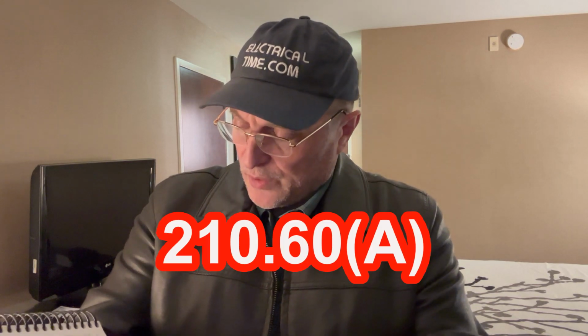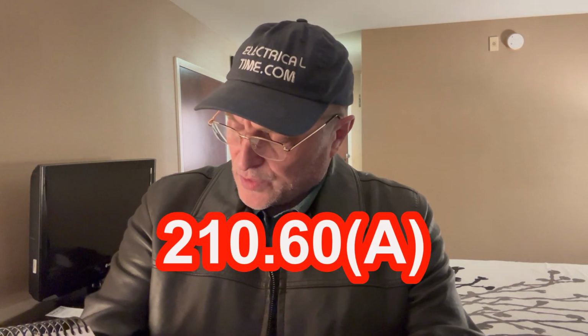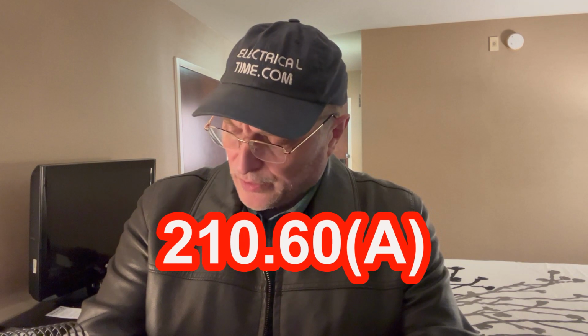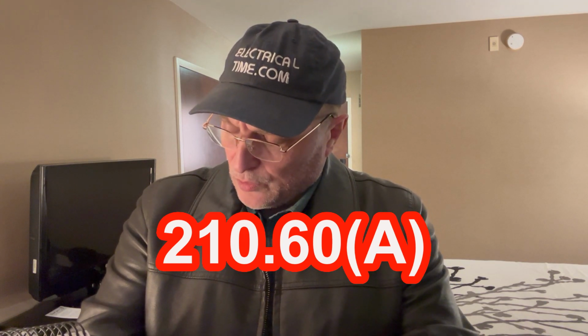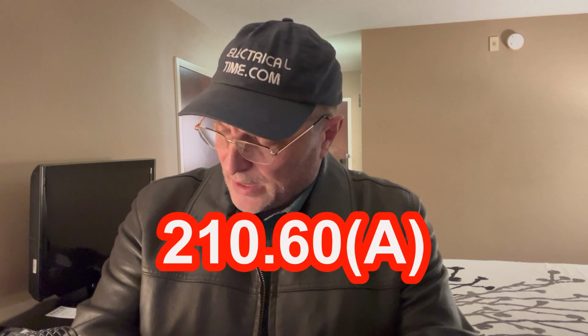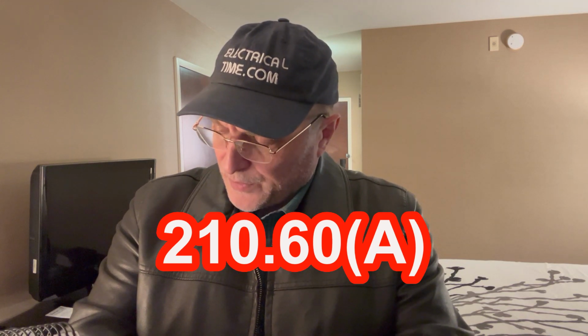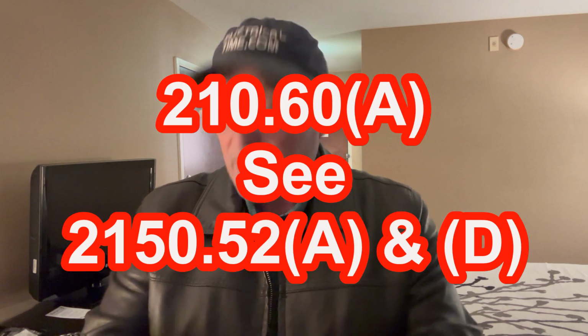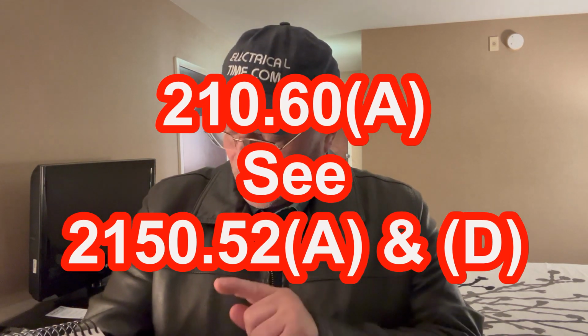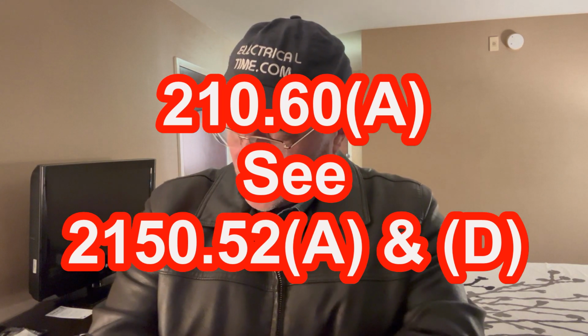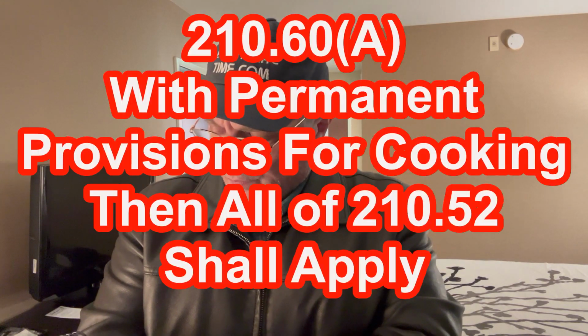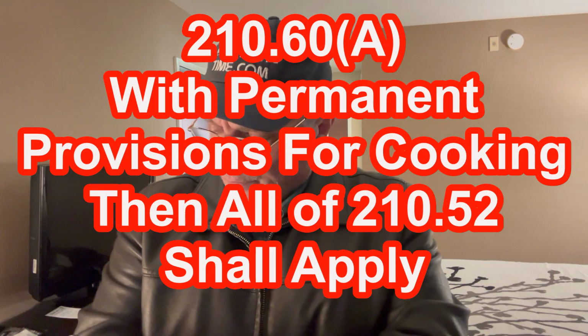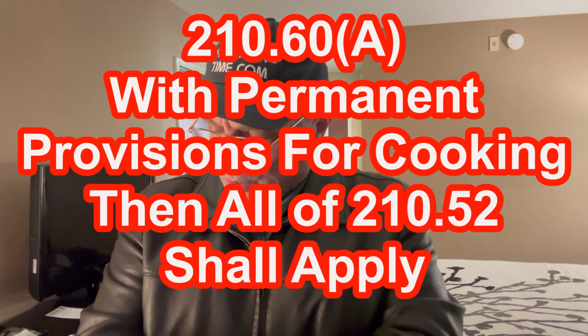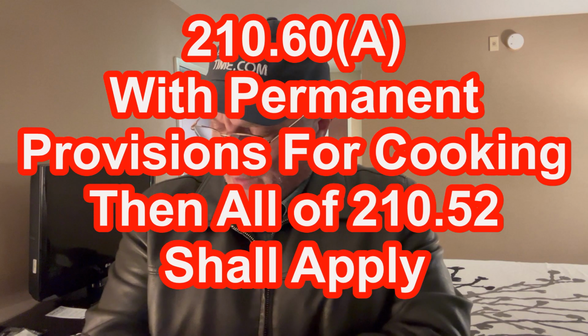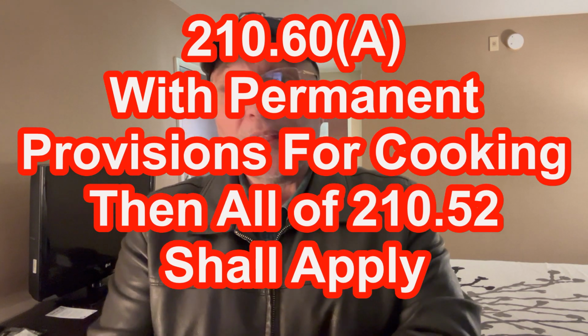A, general. Guest rooms or guest suites in hotels or motels, sleeping rooms in dormitory units, and similar occupancies shall have receptacle outlets installed in accordance with 210.52A and D. And then it says, guest rooms or guest suites provided with permanent provisions for cooking shall have receptacle outlets installed in accordance with all of the applicable rules in 210.52.